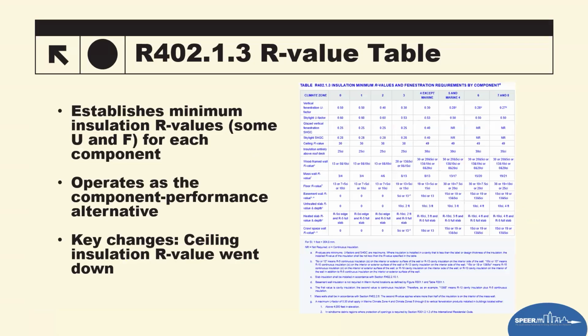The R-value tables are also your go-to reference for the component performance alternative. Each component has to meet what's required in the table. This is just one pathway through the code. One thing to note is that the 2024 edition has some relaxed ceiling insulation minimums, for example R49 going to R38 in some zones. This helps with cost and affordability of construction, but there were other things added, which we'll see at the end of residential, as to why that was able to happen.